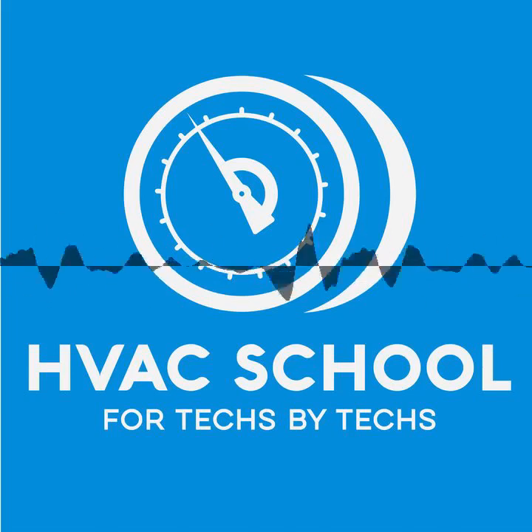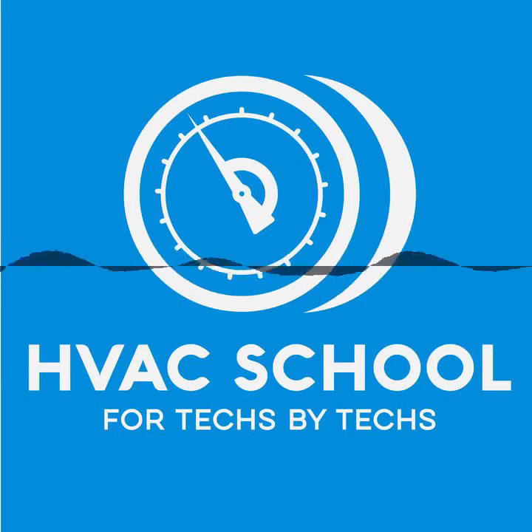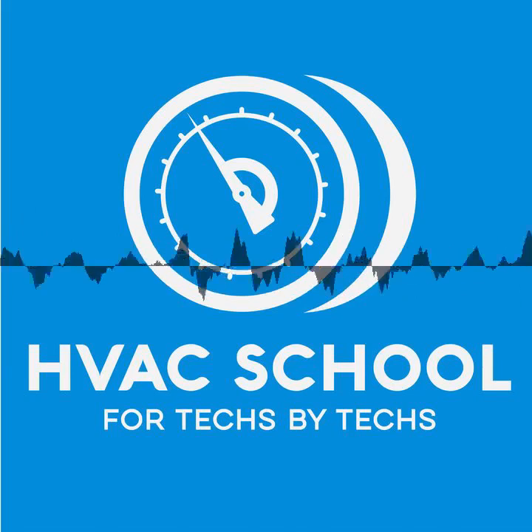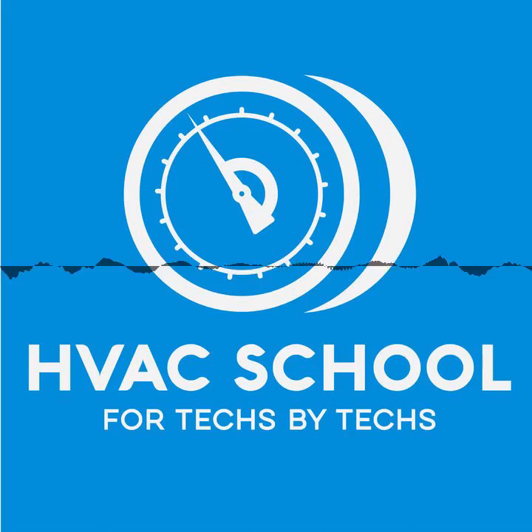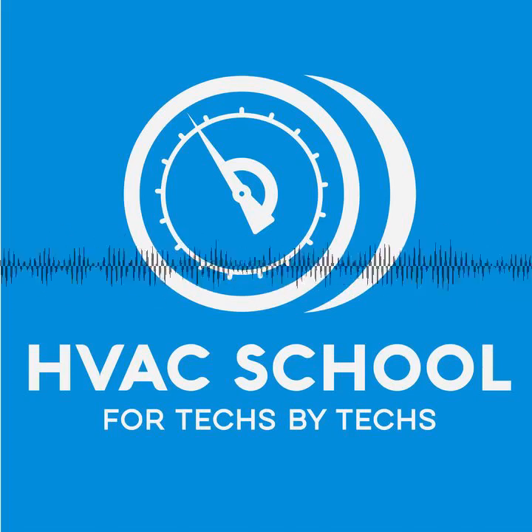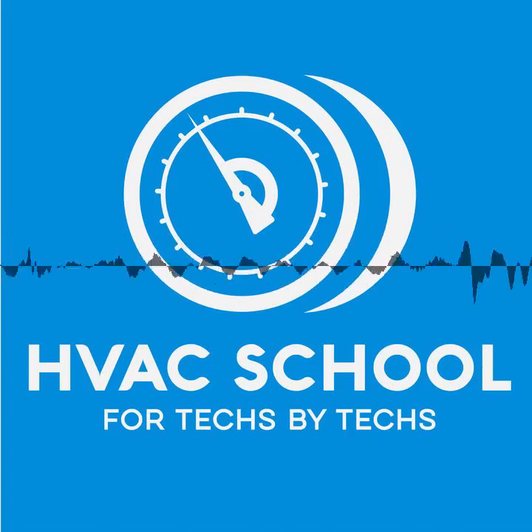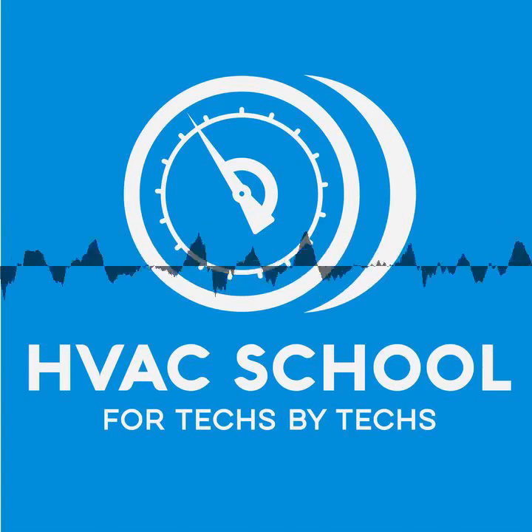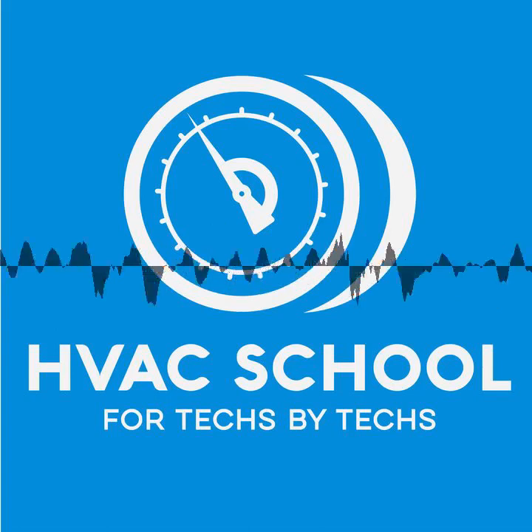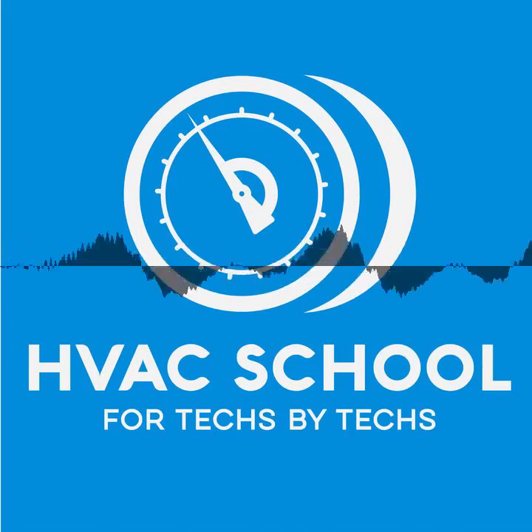Humidity is such a big deal. You can save $10-20 a month on electricity, but if you're not dehumidifying properly, you're not getting value for those energy savings. If you have high humidity, people feel uncomfortable — and what's the first thing they do with their thermostat? They drop it another two degrees, and there go all your savings and more. You need to find that balance point; we can't do one and ignore the other. The intelligence behind a metering device can make a huge difference here.